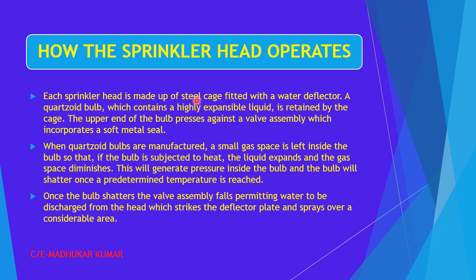How does the sprinkler head operate? This explanation is sometimes asked in the orals, so it is explained over here. Each sprinkler head is made up of a steel cage fitted with a water deflector. We have seen the diagram earlier. A quartzoid bulb contains a highly expandable liquid and is retained by the cage. The upper end of the bulb presses against the valve assembly, which incorporates a soft metal seal. When quartzoid bulbs are manufactured, a small gas space is left inside the bulb, so that if the bulb is subjected to heat, the liquid will expand and the gas diminishes. This will generate pressure inside the bulb, and the bulb will shatter once the predetermined temperature is reached.